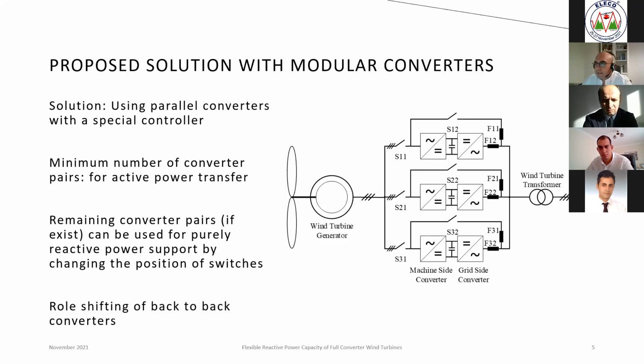Let me explain an example case with 3 parallel converters. If the instantaneous active power is below, say, 1/3 of total capacity, the first converter pair will be responsible for the active power transfer, and the remaining 2 converter pairs will be available for enhanced reactive power capability. In that mode, the switch positions will be opposite to the first converter pair, and the machine side converters will also contribute to reactive power support in addition to the grid side converters. A seamless transition from the machine side role to the grid side role, by changing the controller type, is possible to apply.